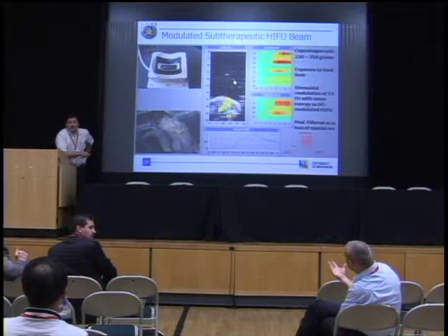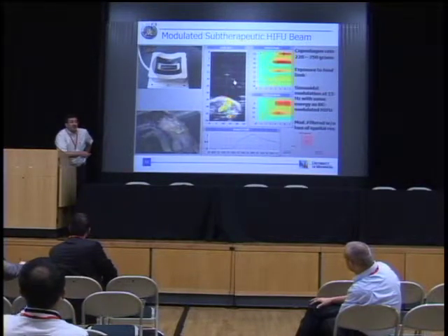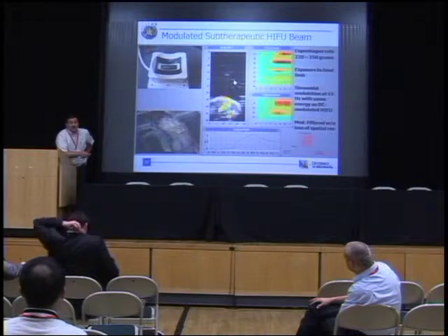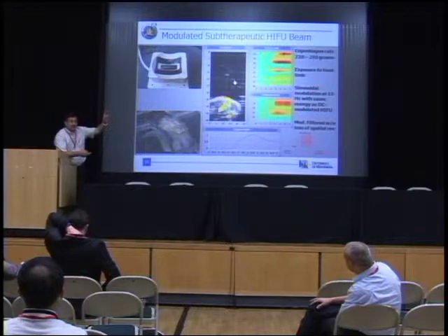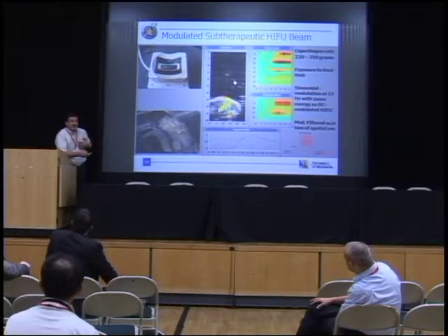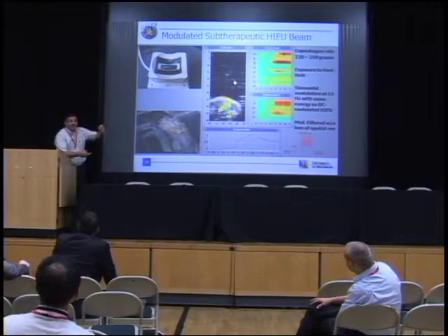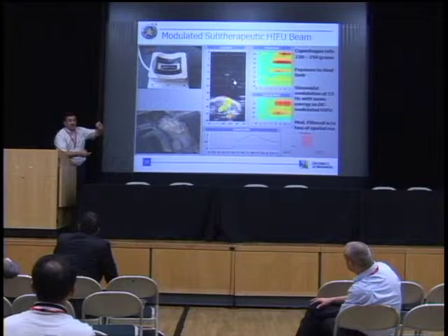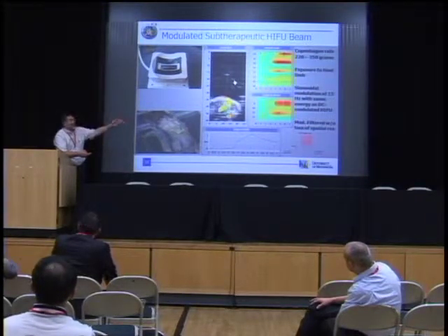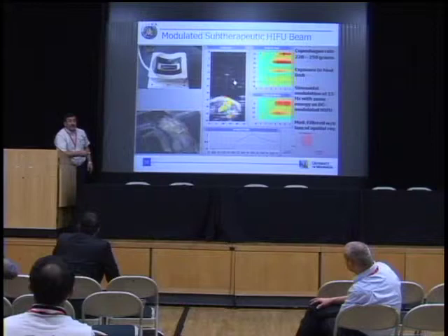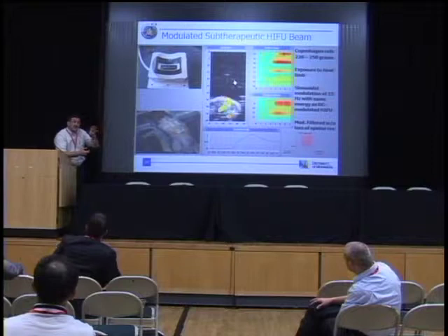That's an excellent point, and that's really one of the main limitations of ultrasonic techniques, that everything that we do is tissue dependent. So when we do things in the lab, in vitro tissue like heart muscle and liver tissue, we have characterized fully, and we have the exact parameters, and we have comparison with thermocouples, and it works exactly right. With tissue in vivo, I do need better anatomical imaging, and I'm going to show just an example of a cross-section of the kind of tissue, with the muscle groups and so on. So I need to have a better estimate of this parameter.